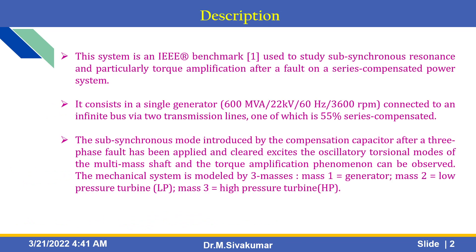The system is an IEEE benchmark used to study sub-synchronous resonance, particularly torque amplification after a fault on a series compensated power system. It consists of a single generator connected to an infinite bus via two transmission lines, one of which is 55% series compensated. There is a sub-synchronous mode introduced by this compensation capacitor.